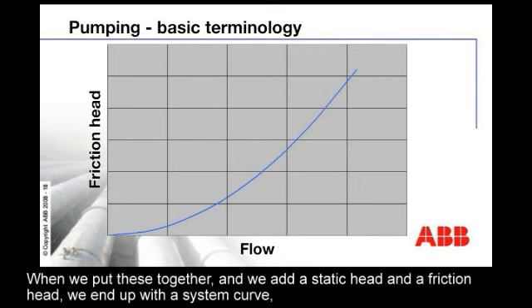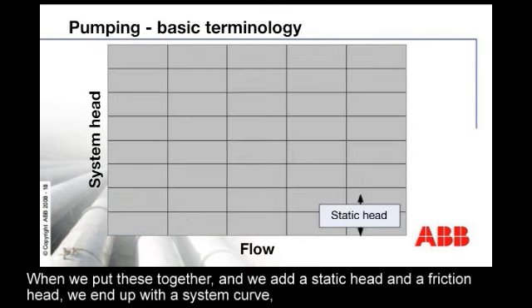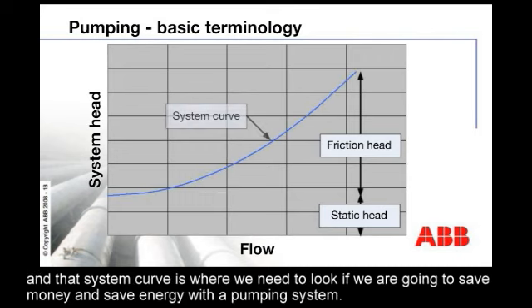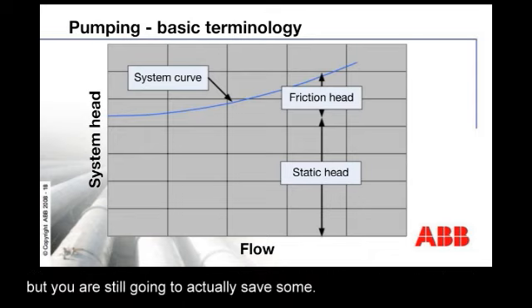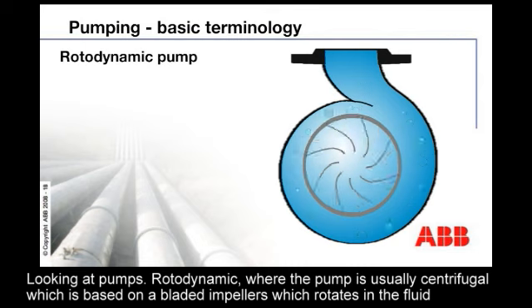When we put these together and add a static head and a friction head, we end up with a system curve. That system curve is where we need to look if we're going to save money and save energy with a pumping system. Where the static head is relatively high compared to the friction head, there is actually less capability of saving money, but you're still going to save some.